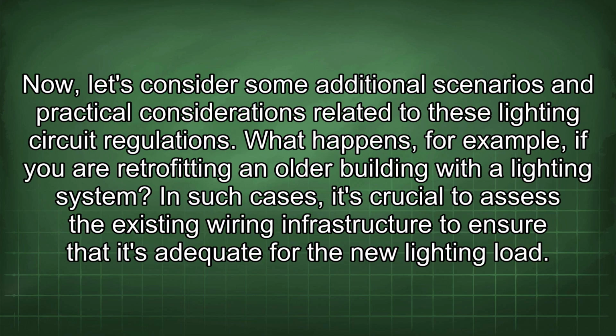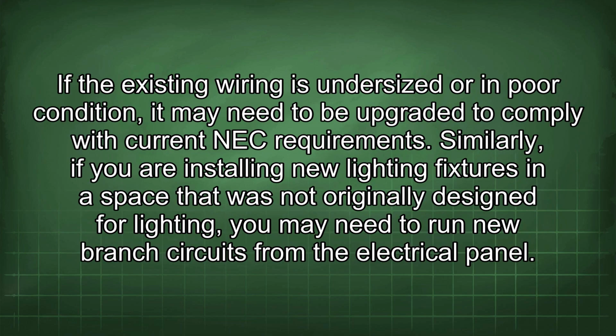Now let's consider some additional scenarios and practical considerations related to these lighting circuit regulations. What happens, for example, if you are retrofitting an older building with a lighting system? In such cases, it's crucial to assess the existing wiring infrastructure to ensure that it's adequate for the new lighting load. If the existing wiring is undersized or in poor condition, it may need to be upgraded to comply with current NEC requirements. Similarly, if you are installing new lighting fixtures in a space that was not originally designed for lighting, you may need to run new branch circuits from the electrical panel.